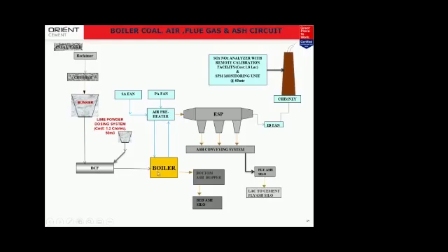Initially, when we started the plant, we faced some hiccups to fine tune it. But once we were able to fine tune the amount of lime powder to be dosed into the bunker, we are now well within the limits of the CPCB norms. Once it goes into the boiler, obviously it burns along with the coal, and it reduces the SO2 emissions.